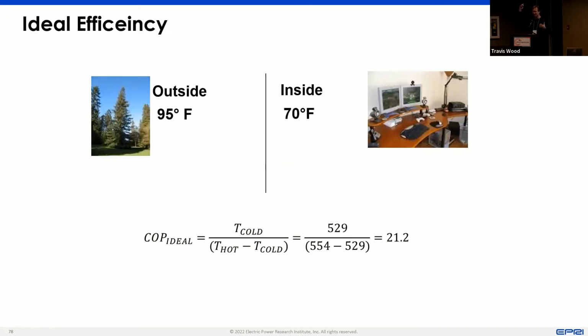So just think of it this way: the bigger the temperature difference, the less efficient it ultimately can be. If it's a 95 degree day outside and we'd like to keep our inside at 70 degrees, the maximum possible efficiency you can achieve with an air conditioner or heat pump is 21.2, meaning that if you put one unit of energy in, you should be able to move 21.2 units of heat out of your house. That's not realistic, but we'll get to that.